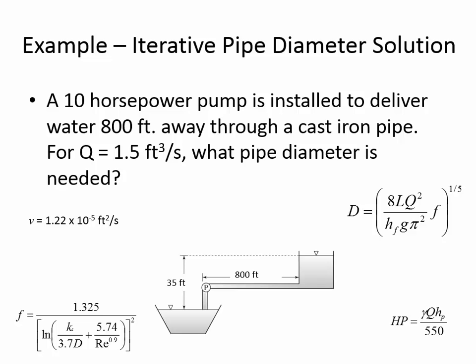And so why have I asked you to get Excel out? It's because every time we change the diameter, it's going to change the F value, and it's going to change the velocity. And so that could be a really tedious problem if you try and iterate that by hand. The main thing is how big should the pipe be? If we've got 23.8 feet of head available to push that water along, and the flow rate, we wanted a certain flow rate.